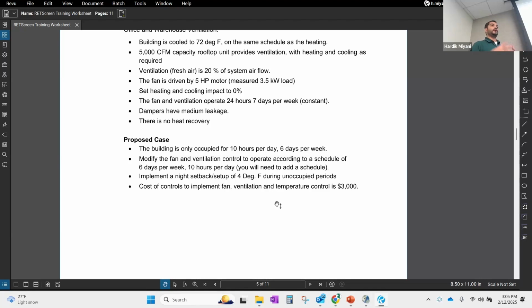Optimum start stop is a sort of control measure where the building management system, like the controls, will decide what is the best time to start your system. Okay. So right now, the way the industry operates, the building engineer who maintains the building decides, okay, tomorrow the temperature is pretty cold, let me start my system a little early, like 4 a.m. It is based on guess or experience. But over here, optimum start stop is something where the controls will decide what is the best time to start. It takes into consideration multiple factors. So it takes what is the set point you want to reach, what is the outside temperature, right?